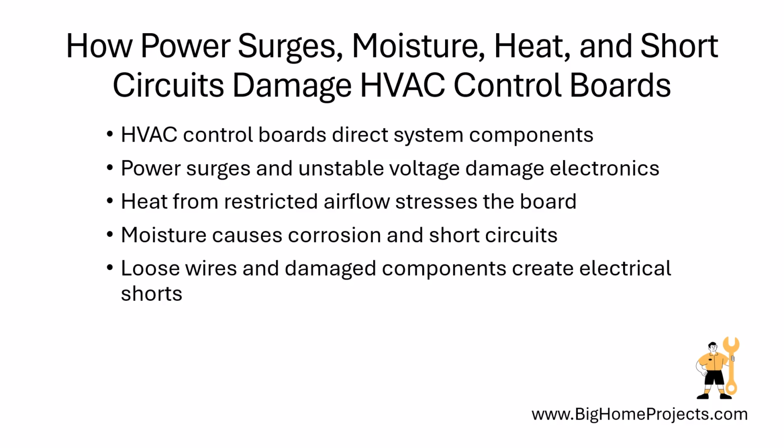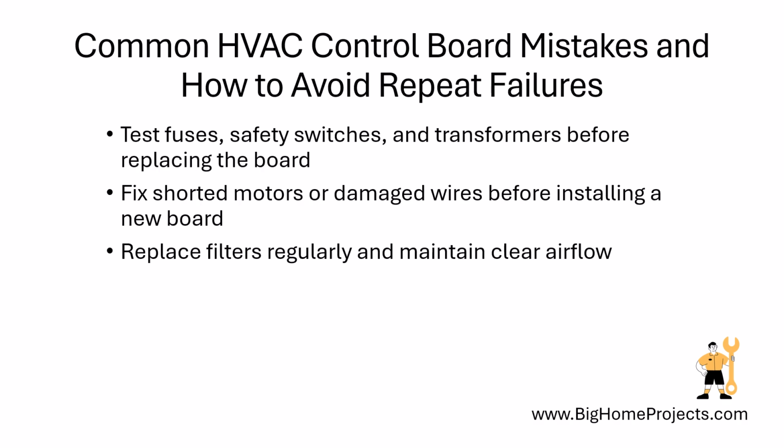Before replacing a board, turn off power, inspect the wiring, check the low-voltage fuse and transformer, clear the drain, and confirm that connected motors and controls are not causing the failure. A common mistake is blaming the board when the real problem is a blown fuse, open safety switch, or failed transformer, so test those parts first.